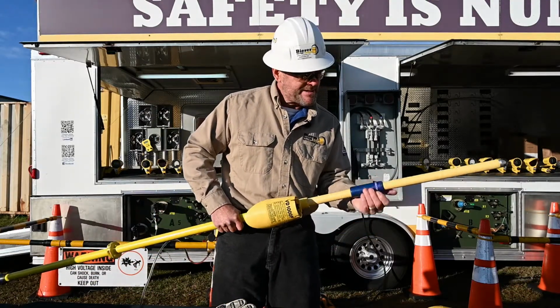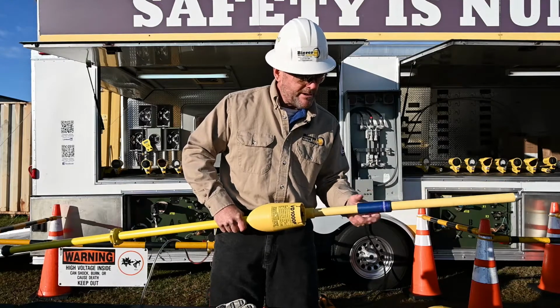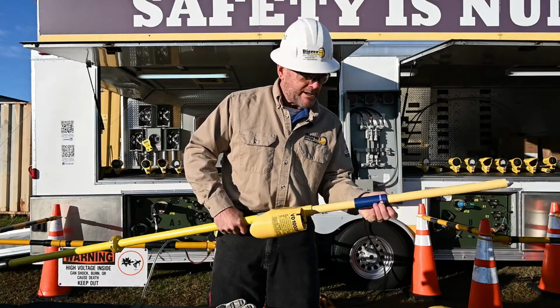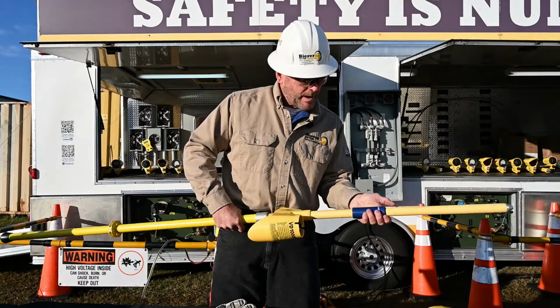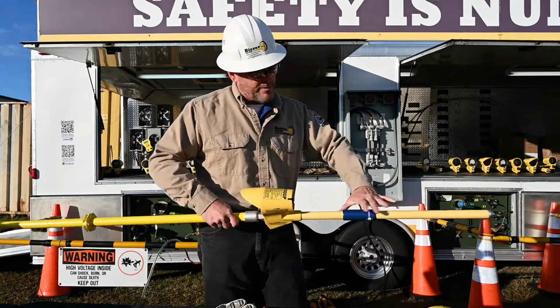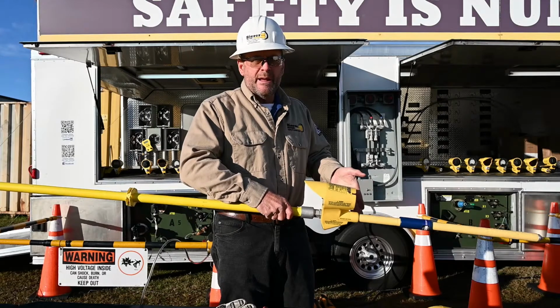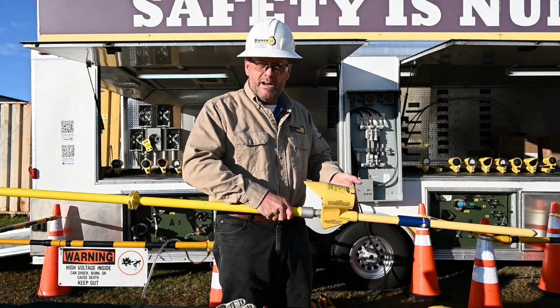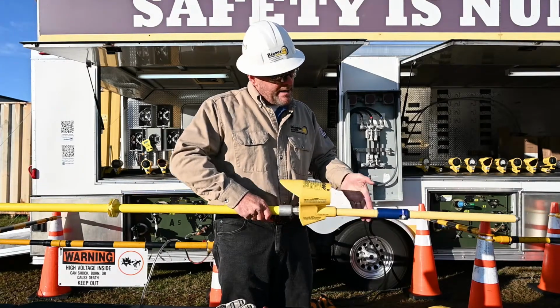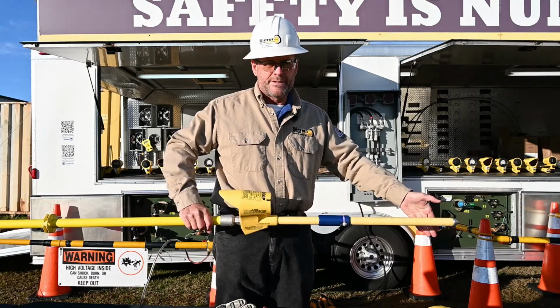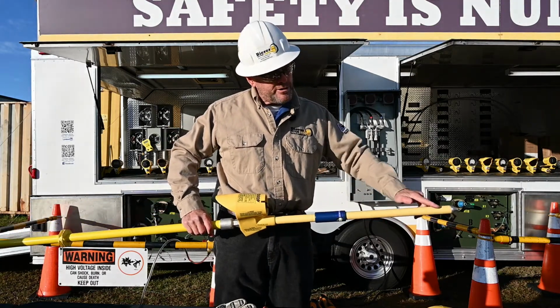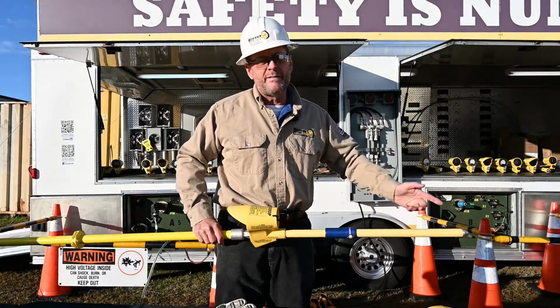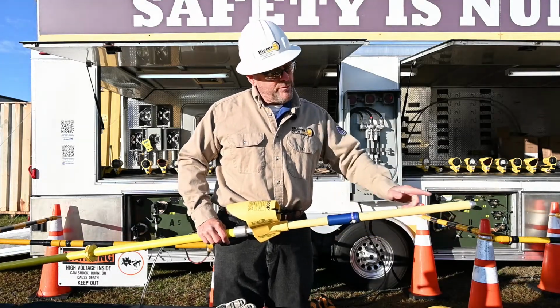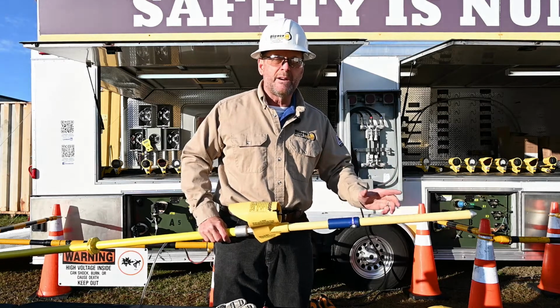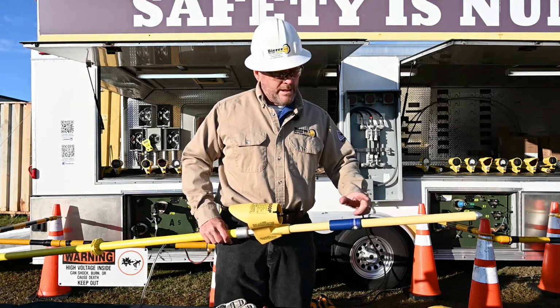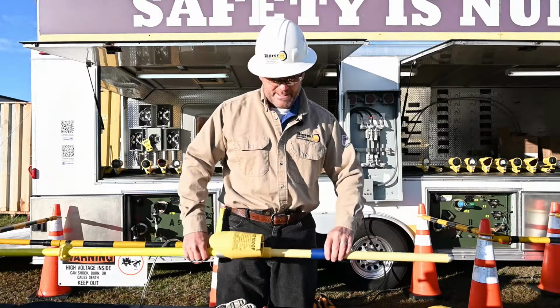You simply place that 0 ohm extension onto your meter, that cone tip, the probe, and you can see by using that 0 ohm extension, you're going from here, that potential arc flash, or you've got a hot bus here - you go from here, now you're here, and you will never have an arc flash. So you're not going to use a 0 ohm extension all the time, obviously, but it's good to have one in your kit, so when you have that scenario once in a while, you have that protection, that device, that accessory.